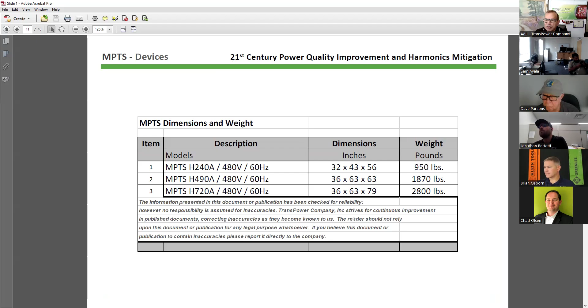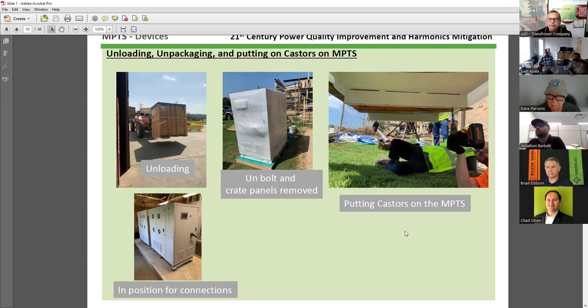In places where local law overrides the IEEE or NEC codes, OSHPD in California requires all equipment to be firmly bolted to the ground. Even though there have been pilot and due diligence projects in California installed on lockable casters, where all the wheels have locks, and once locked you still need conduits, so the conduit itself prevents the MPTS from rolling away. But in California, general practice is that you are not allowed to keep it on wheels. Good question, thank you.